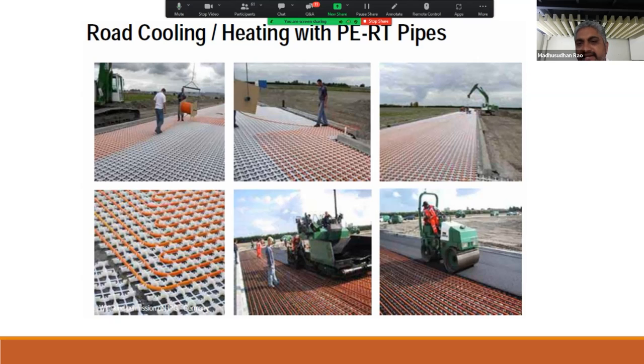But since these are embedded in the building structure, what we recommend, and what is recommended by the standards, is also to have an oxygen diffusion barrier so that oxygen doesn't diffuse. The life of these pipes is more than 100 years. I can show that. We generally suggest PERT, but no particular love for PERT, except that PERT is recyclable, PEX is not. So that's the reason why we usually suggest PERT, but there are projects which are using both kinds of pipes. It doesn't matter.